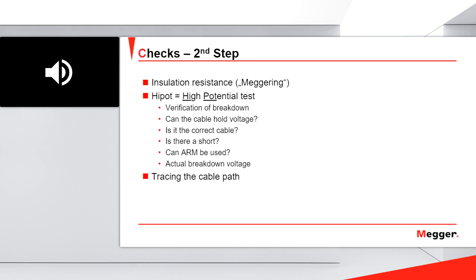Okay. This is very important because, for instance, if the fault I am trying to find is a short between the conductor and the concentric, I will not be able to charge the cable. But if I have a pinhole, a perforation in my insulation, maybe I will be able to charge the cable with 3, 4, or maybe 5 kVs. Okay, so that is very important because the breakdown voltage of the fault gives me information about what type of fault my cable has. So for that reason, this step is very, very important.